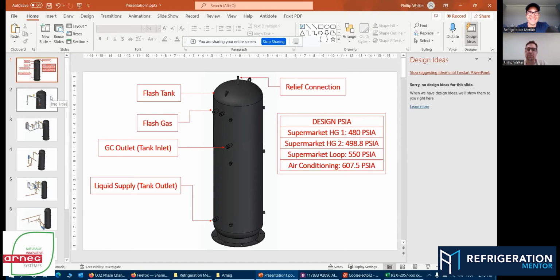We're doing a lot of mixed-use buildings right now, and when you get into mixed-use buildings, there are more stringent codes. Bringing in a synthetic refrigerant may not be the best means for the developer, right? And you're sure as heck not going to bring in, unfortunately, another synthetic refrigerant. We're limited in propane, and you can't bring in ammonia for a mixed-use building. So we're left with CO2.